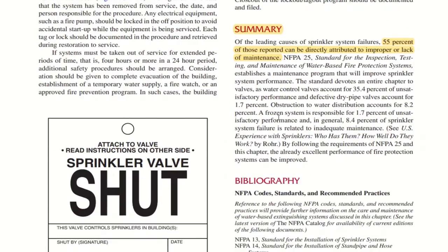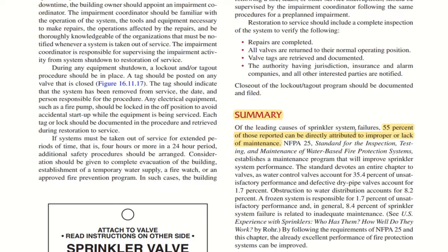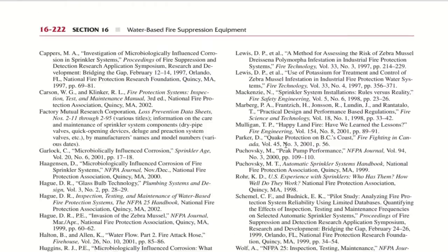And here in summary, just go through the leading causes of sprinkler system failures: 55% of those reported can be directly attributed to improper maintenance or lack of maintenance. So this is an important topic, so you might get a question from this particular chapter as well. So NFPA 25 is covering the inspection, testing and maintenance of water based fire protection systems.